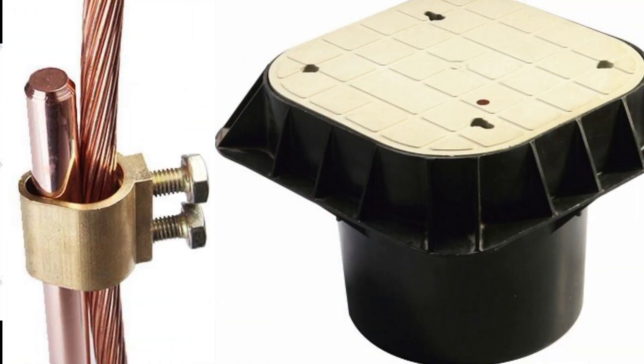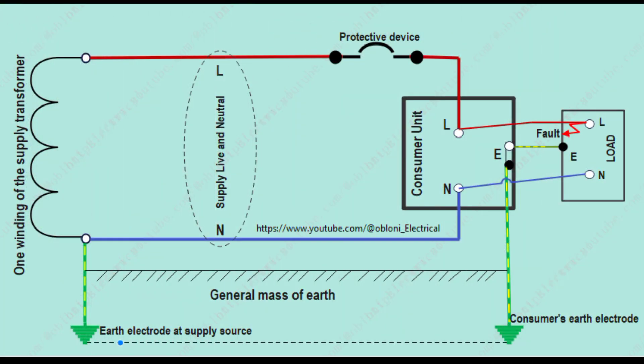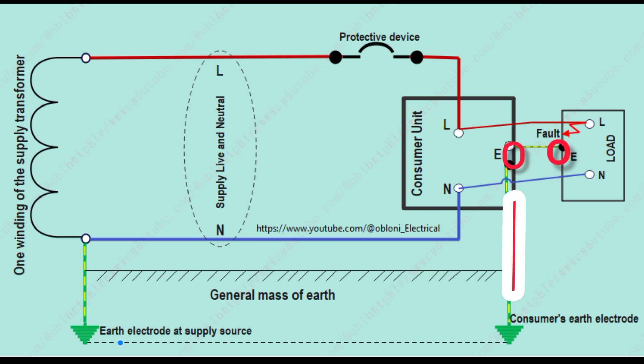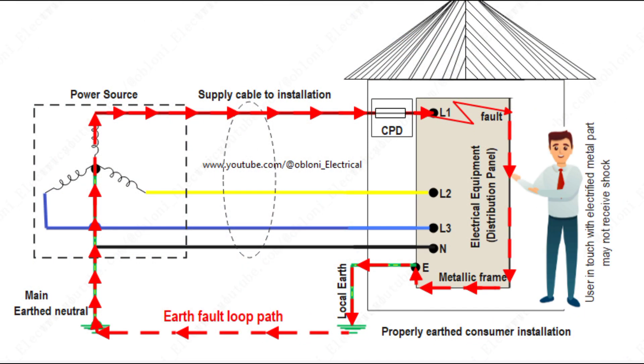In a TT earthing arrangement, all metal parts of the consumer's installation must be properly connected to the general mass of earth by means of an earth electrode. We have to bury that earth electrode in the ground. The reason for doing that is to provide a low resistance path for fault currents that may occur between live conductors and any metal parts in that installation, to flow to the general mass of the earth freely.